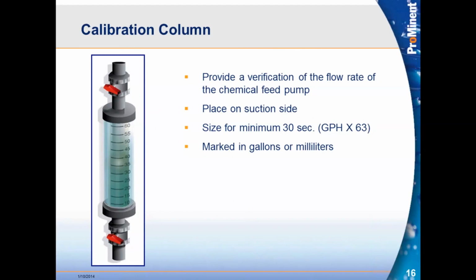One other accessory you'll see very commonly on a skid is a calibration column. Historically, people have done this. It's nothing new with a metering pump. They're going to take the calibration column and time it and do a drawdown test. We do that on the suction side of the pump. We can't pump back into the calibration column and get a good representation of what the pressures are in our system. So we can't pump into the calibration column to do that calibration test. So we want to do it off of the inlet, or it's going to provide fluid to the inlet of the pump. And we want to size that for at least 30 seconds of drawdown.